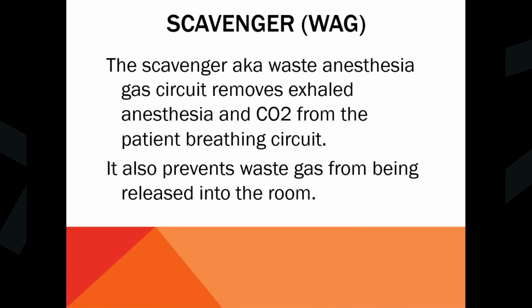What you put into the patient, you have to eventually take back out. And if you can't take out at the rate that you're putting it in, then that creates a number of issues on the clinical side, as well as what the machine's going to do. So if you're getting some really bizarre issues with your anesthesia and your ventilator, your scavenger or your WAG may very well be the source of your problem.